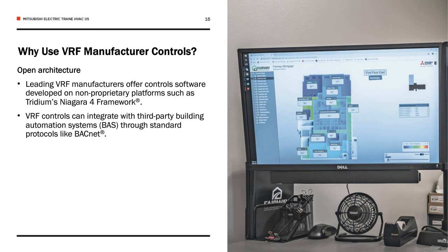Some leading manufacturers in the VRF industry offer control software and non-proprietary platforms such as Tridium's Niagara framework. In this situation, VRF controls can integrate very easily with a third-party building automation system and third-party equipment. The most standard protocol that's used today is BACnet, though multiple open protocols are available and can be used.